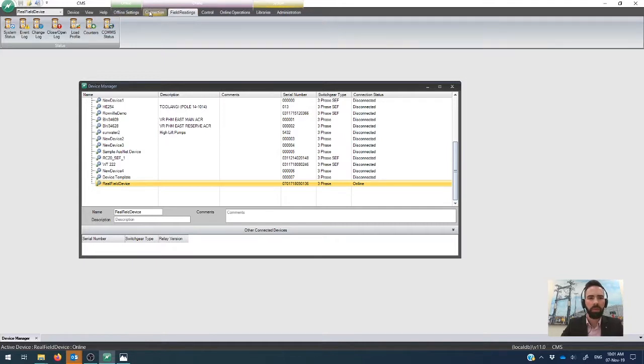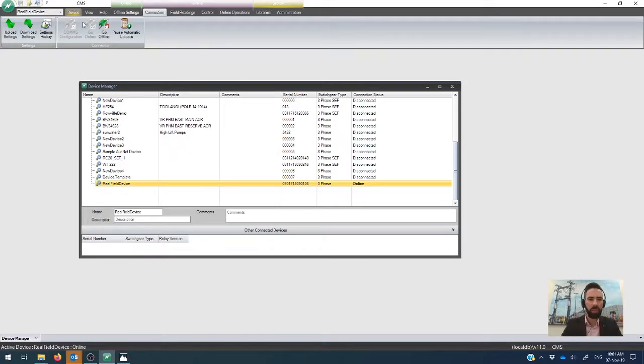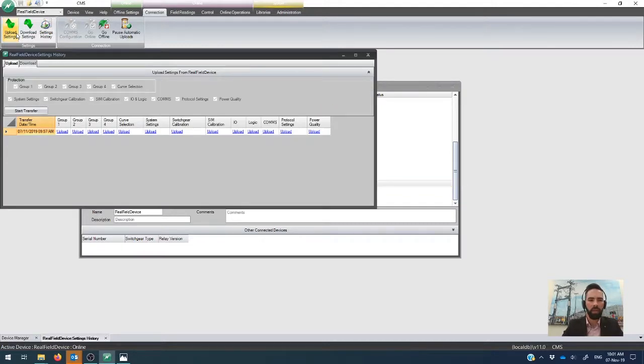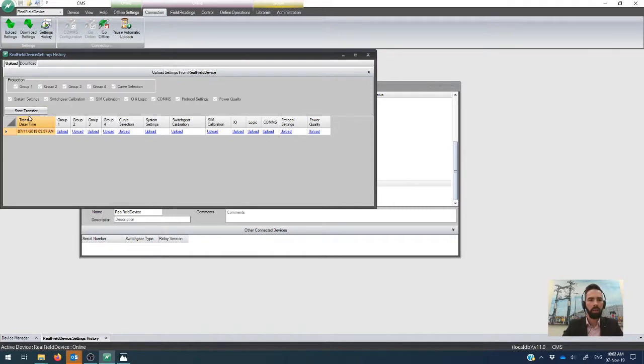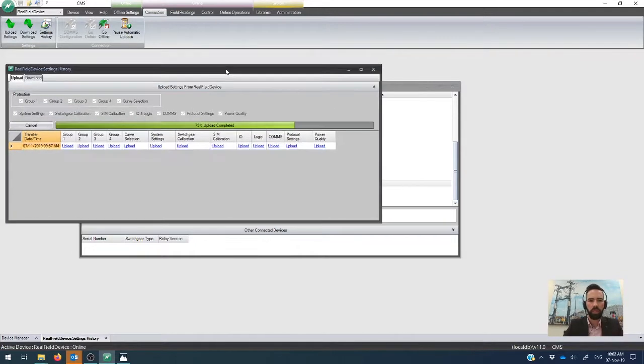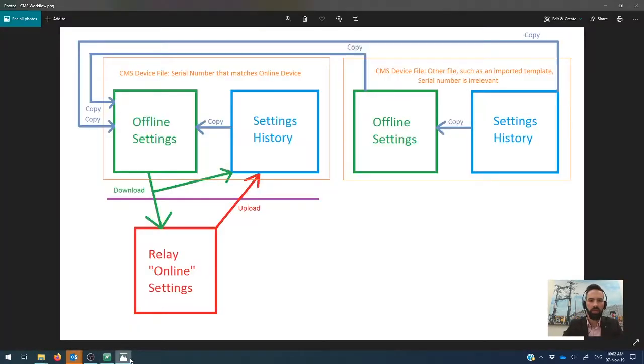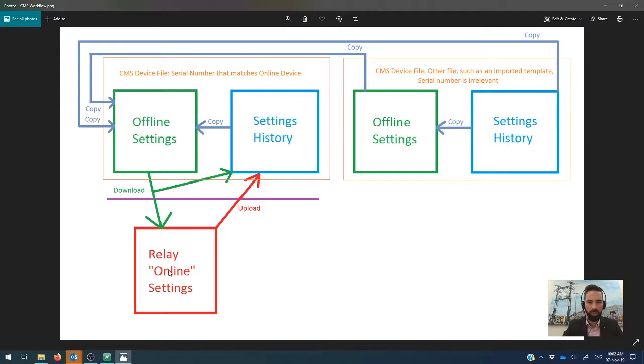Okay. So if we want to do an upload, so we want to pull the settings from the device into the CMS device manager, you go to upload settings over here. And you'll see that all of the different settings parameters and history and all the rest of it, that is automatically ticked here. We automatically bring everything out of the controller. So we click start transfer. All right. So that is then pulling all of the settings out of the controller and storing it in the settings history, which if we flick back to this side here is this component associated with this CMS device file.